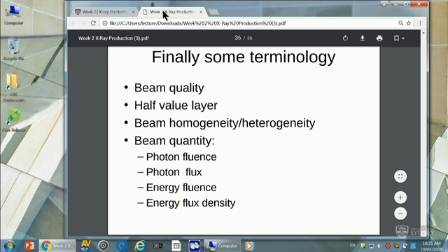It's really subjective. What you can do, though, is if I say to this fellow, go and X-ray this dosimeter at 70 kVp, and you do the same at 70 kVp, and tell me the amount of aluminium that will reduce the intensity by half, we've now got a much more accurate description of the different energies in those two X-ray rooms. The half value layer is a really good standardized measure of establishing the relative energies between different X-ray rooms.